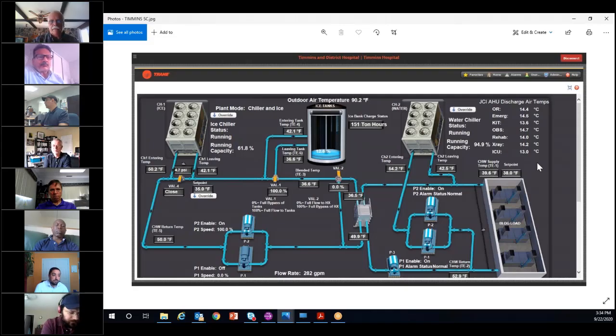So this one, we essentially burn as much ice as we can through that period, knowing that the utility rate is pretty well fixed for the specific customer. For a customer that may be a Class A customer or may have a special hydro rate or fluctuating hydro rates, of course, that control strategy would have to be modified for that specific customer. But this one is definitely programmed to just hit the easy button and let it do a similar thing throughout most days, which is, again, going back to discussing with the customer what they wanted and what is going to ultimately get the results that we're looking for. Yeah, for sure. Sounds good.